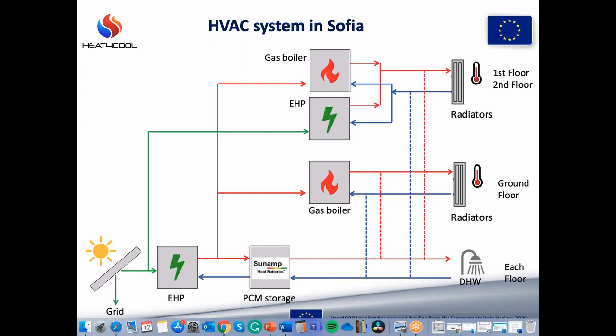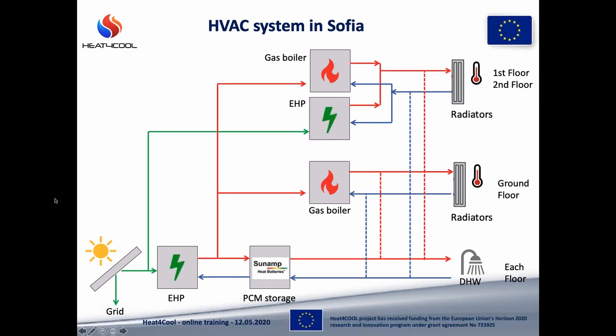Priority will be given to heating of the heat batteries through circulation pump 1. And during the heating season, after the heat batteries have been charged, circulation pump 1 will shut off and circulation pump 2 will be turned on. The pilot building is divided into 3 thermal zones. Each of them is served by a separate gas boiler and is also linked to the heat pump unit.